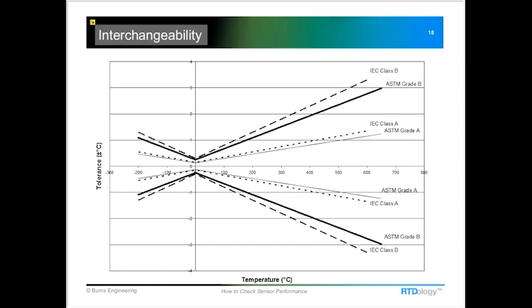Now, the 2 standards will have either the Class B or Grade B and the Class A or Grade A sensors. And right down here at our 0 degree C point on the horizontal axis, we've got our best or tightest interchangeability, because that's where the manufacturers adjust the sensing elements when they're building the probes and putting it all together. But as we go away from 0 degrees C, that tolerance band opens up. And if you look at the lines here, you can see the IEC standard is a little looser tolerance than the ASTM does.